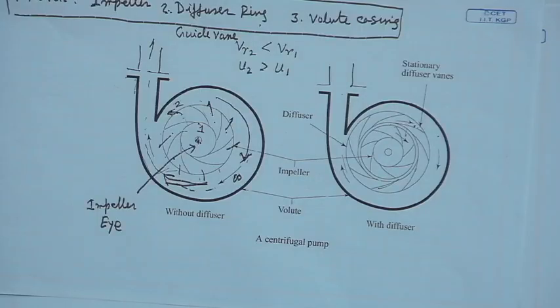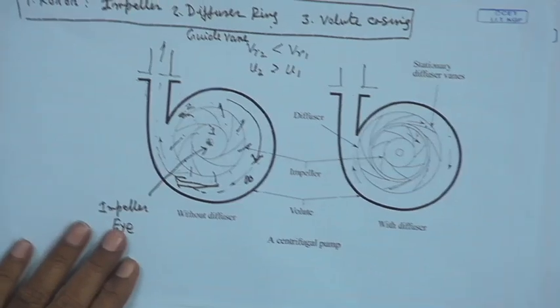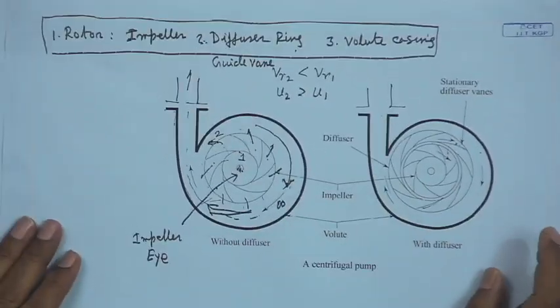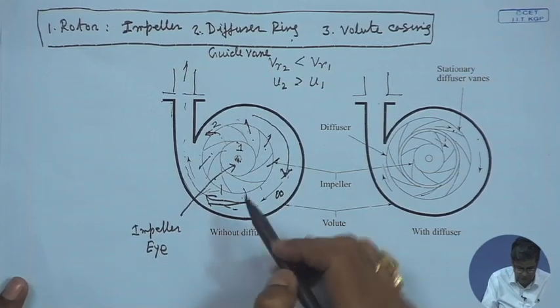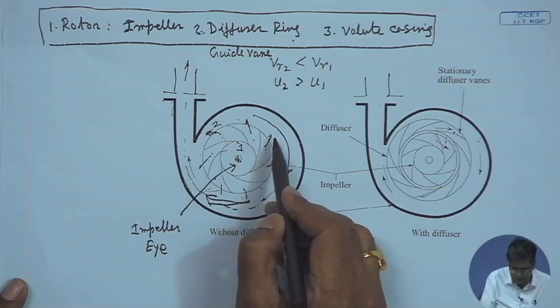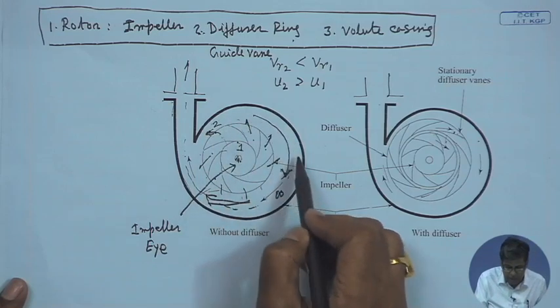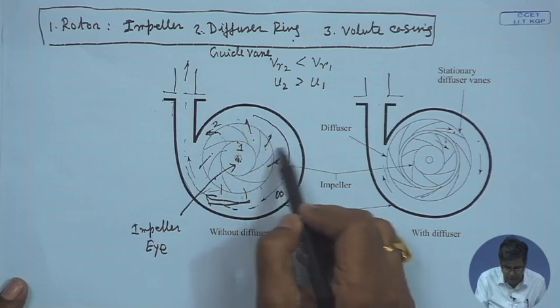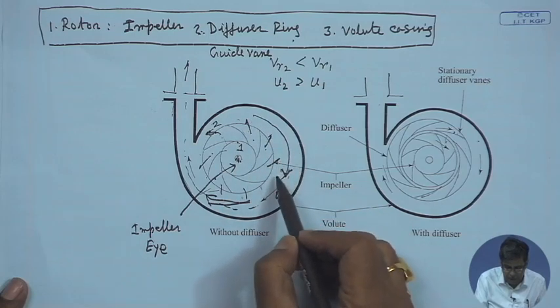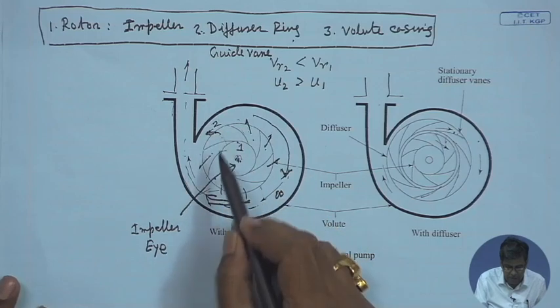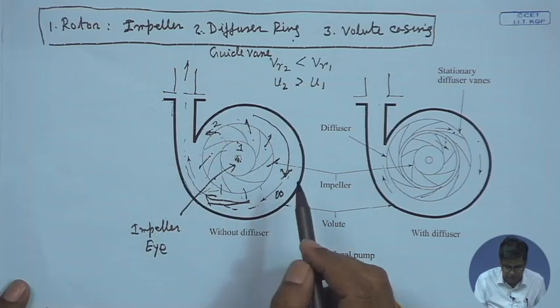The volute is the spiral casing or scroll casing. We already recognized earlier that the impeller has a volute casing, where the flow comes out of the impeller passage into this spiral casing. In the direction of flow, this spiral casing provides an area which is increasing, and ultimately the kinetic head is converted to static pressure head.